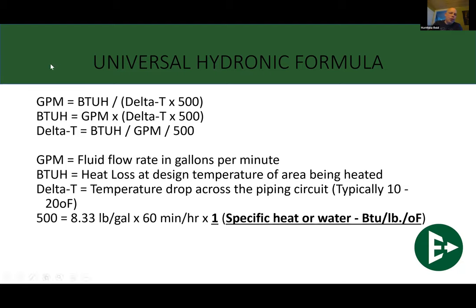We usually base it around the top one: GPM equals BTU divided by delta T times 500. Now, you can see there, and again, you get copies of all this in your email in a couple of days, but I'm going to talk about where these numbers come from. So your GPM, that's your fluid flow rate in gallons per minute. The BTU, that's your heat required to heat the area. Delta T, of course, is your temperature drop. Now the 500, I want to talk about that specifically. Where did that 500 number come from? Well, let me tell you.